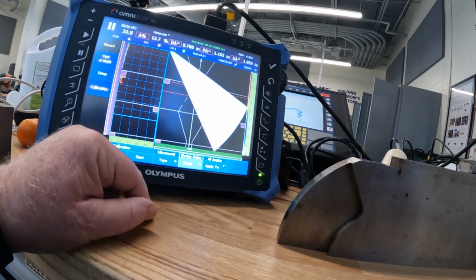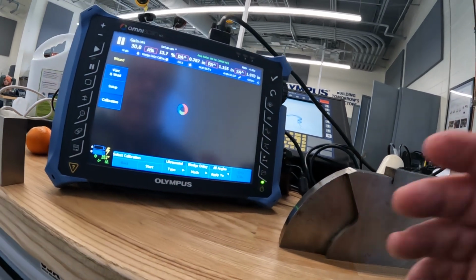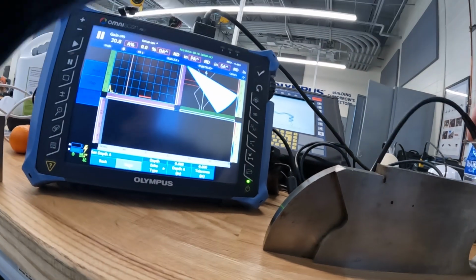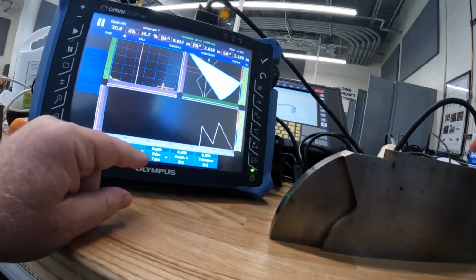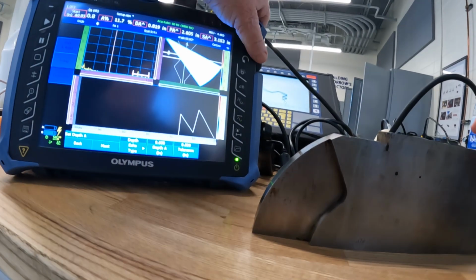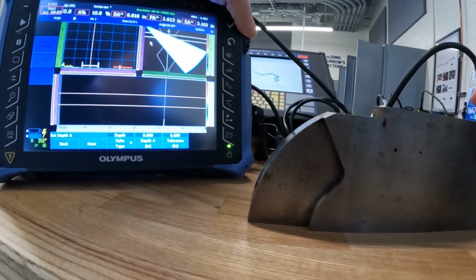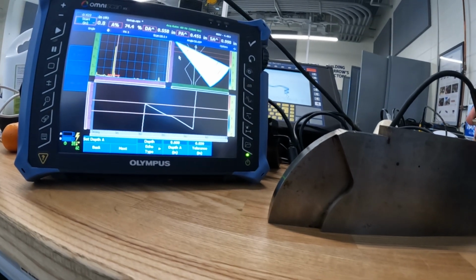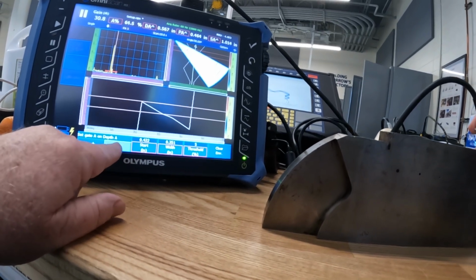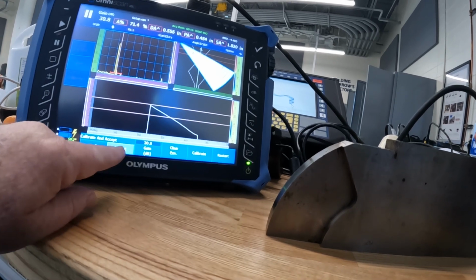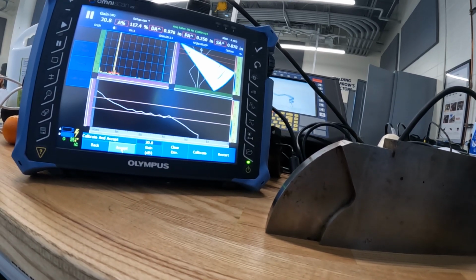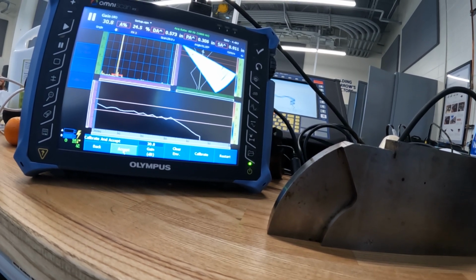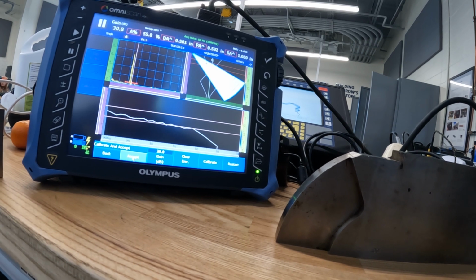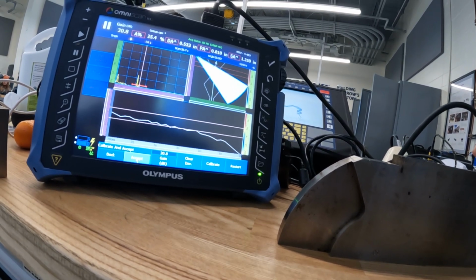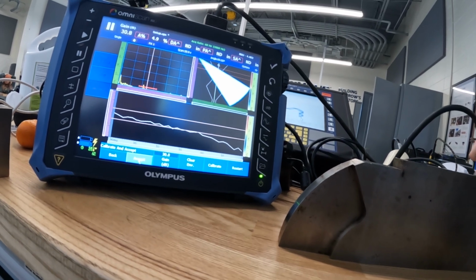So then I'll go to my wedge delay next and hit start, and it automatically will set everything to my drill hole. And I'm going to move my gate up to the drill hole. So we're locked in on the hole. Hit next, next, next. And then I'm going to move across and have it paint my response. And as I move across, it's going to fill in the envelope at the bottom. You notice it trails off to the bottom, so I'll hit calibrate, and then I'll go back across.